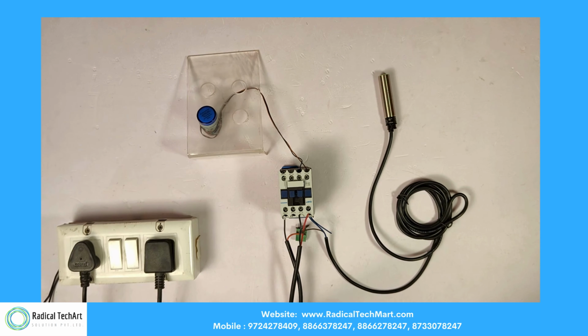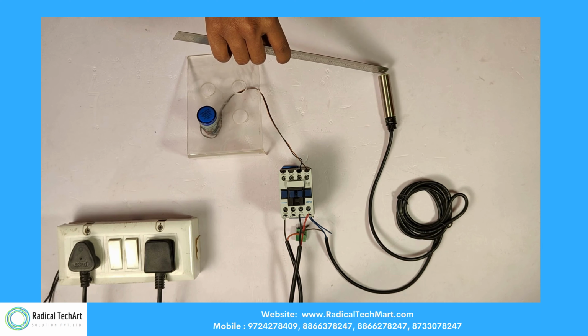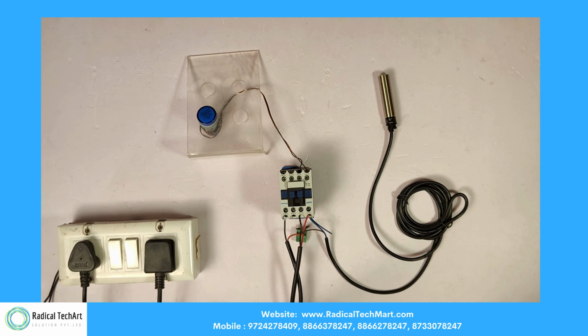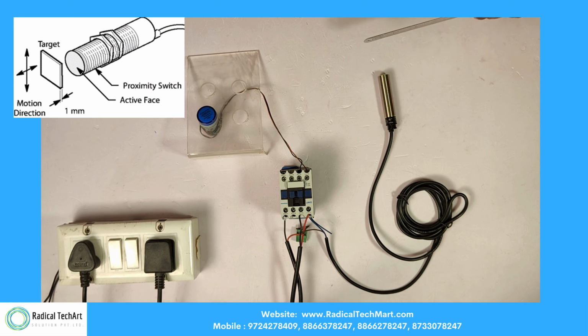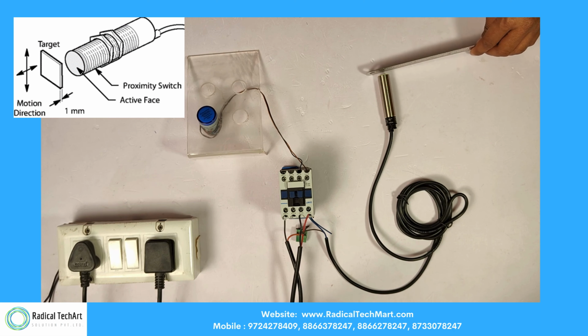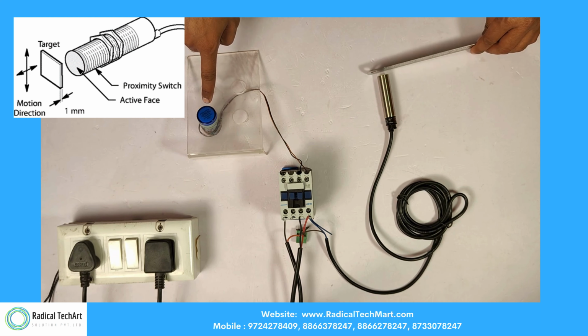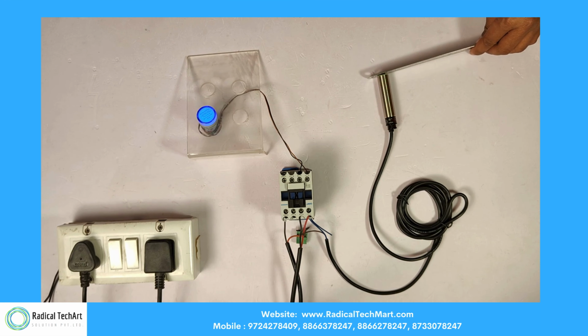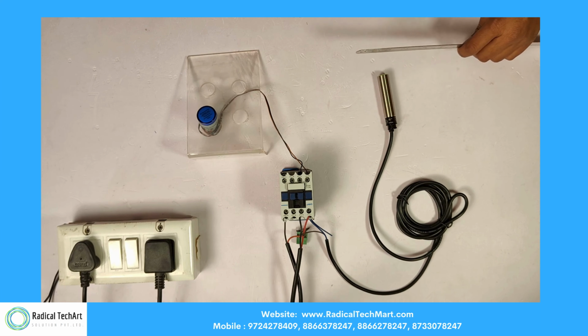Now let's see how it works. First, we will turn on the switch. In the center, we have a contactor for this demonstration, where detection occurs and the sensor switches on when a metal target disturbs that field and reaches the operation point. The sensor switches off when the target moves away from the sensor and reaches the release point. The proximity sensor has a limited sensing range, up to 4 mm maximum, and detects only metal objects.